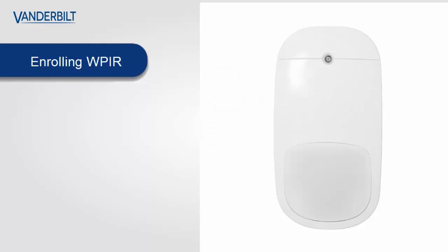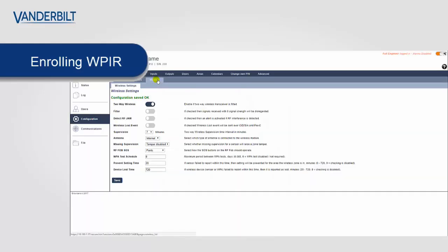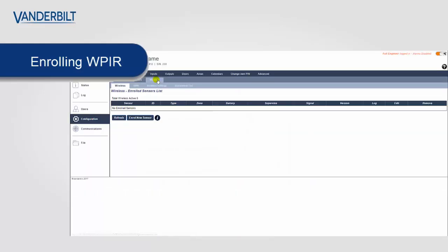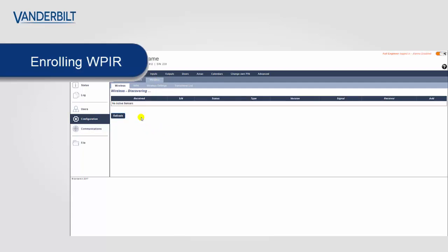I will first demonstrate how to enroll the WPIR as a 12-meter passive infrared detector. We first put the panel into discovery mode. This means that the panel is listening for new devices. We click on the wireless menu and click on enroll new sensor.